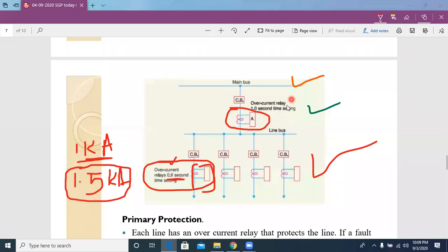Here also the activating quantity of this relay is current, and the type of relay is an overcurrent relay. Its operating time is 1 second, whereas in this relay the operating time is 0.6 second. So there is a discrimination between this relay and this relay in terms of time: here the operating time is 0.6, and here it is 1 second.